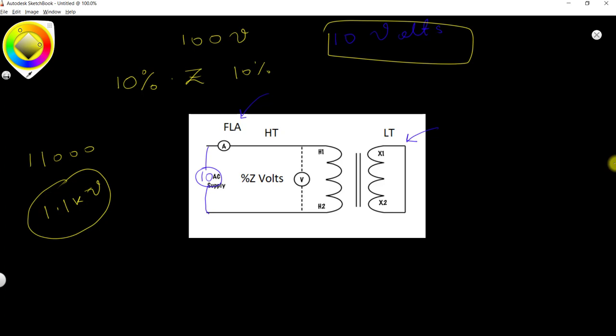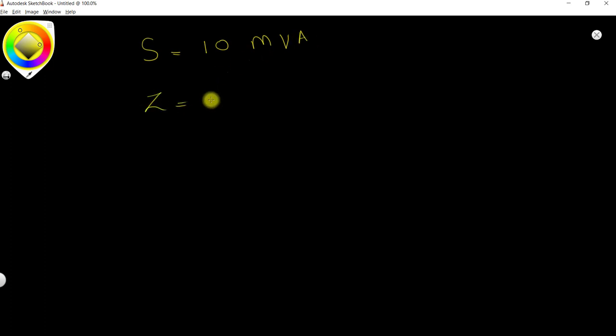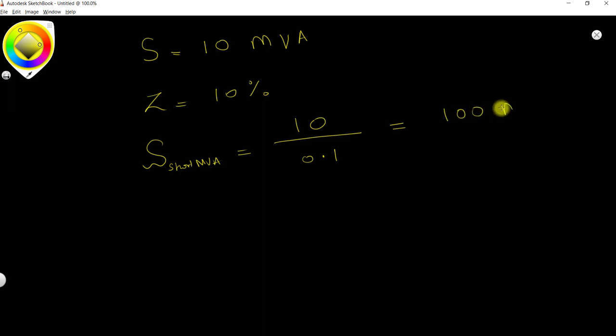Now for short-circuit calculations: consider a 10 MVA transformer with a percentage impedance of 10 percent. You can calculate the short-circuit MVA by dividing the actual MVA by the percentage impedance expressed as a decimal: 10 MVA ÷ 0.1 = 100 MVA. So the short-circuit MVA of this transformer is 100 MVA.